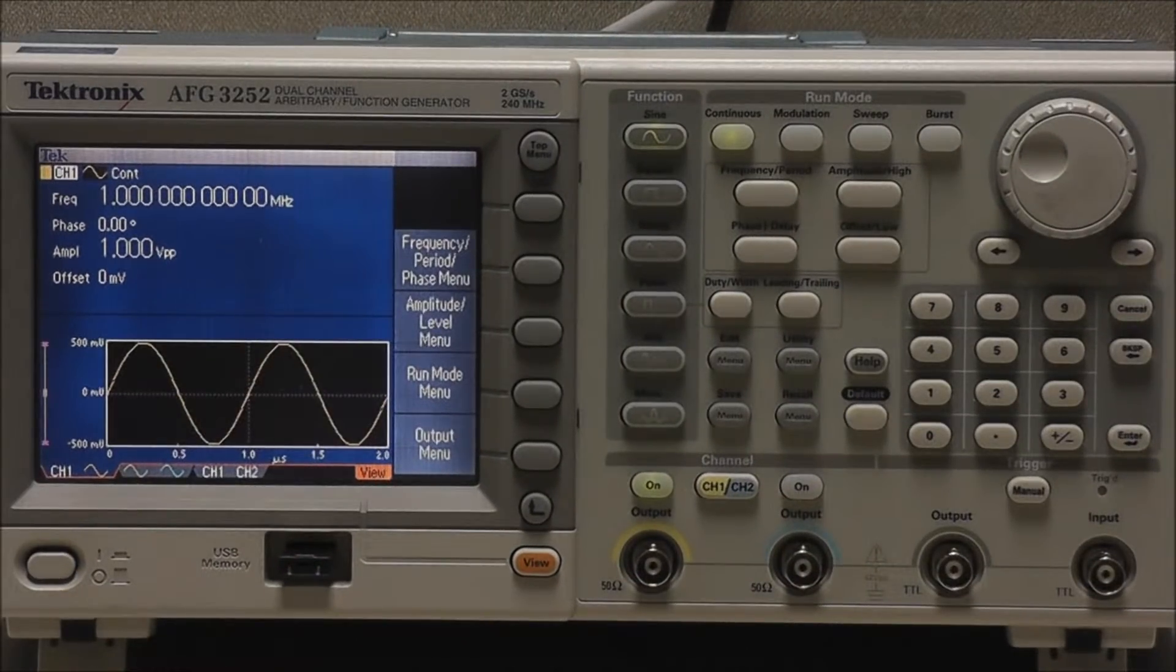We are allowed to save up to four arbitrary waveforms in the instrument's internal memory. It's important to clarify that channels themselves do not receive waveform data, but rather they reference waveform data location.